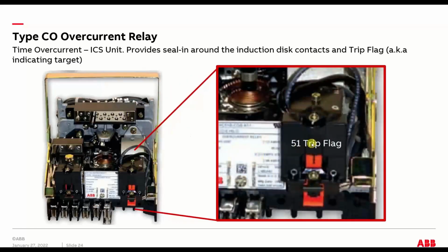This is the last piece. This is just an extra contact, but I noted it because it also contains a trip flag. So the relay actually has two trip flags, one for the time overcurrent element, which is here, and one for the instantaneous. So in this picture here, you can see that this relay had tripped on a time overcurrent.